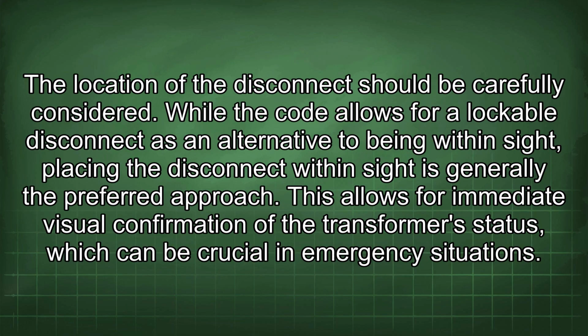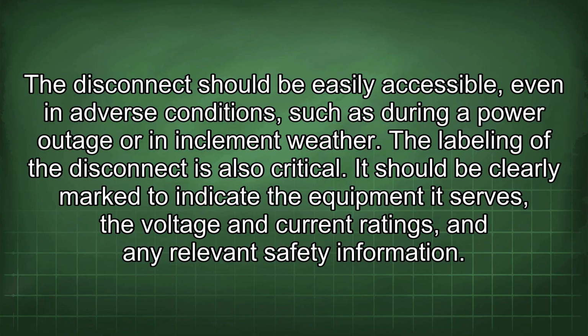The location of the disconnect should be carefully considered. While the code allows for a lockable disconnect as an alternative to being within sight, placing the disconnect within sight is generally the preferred approach. This allows for immediate visual confirmation of the transformer's status, which can be crucial in emergency situations. The disconnect should be easily accessible, even in adverse conditions, such as during a power outage or in inclement weather.